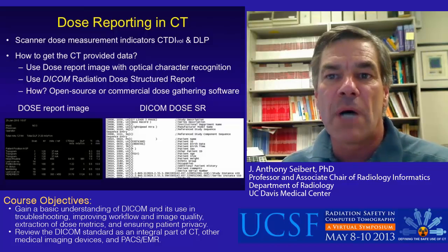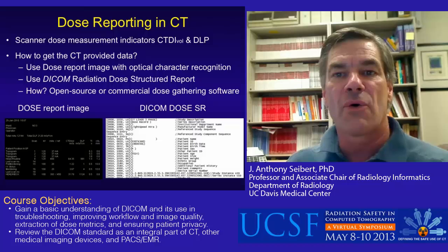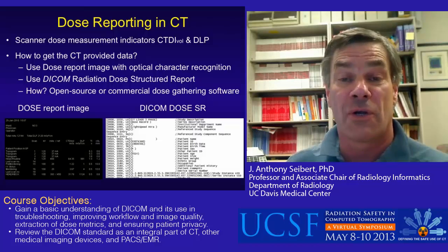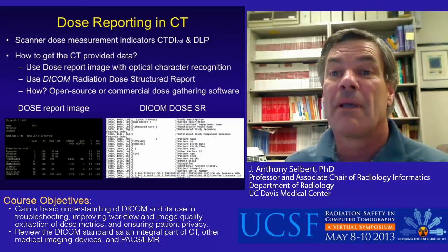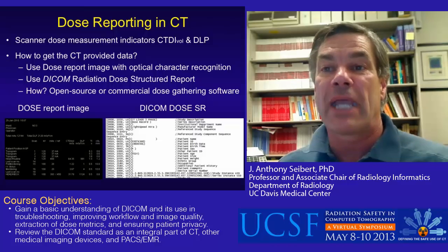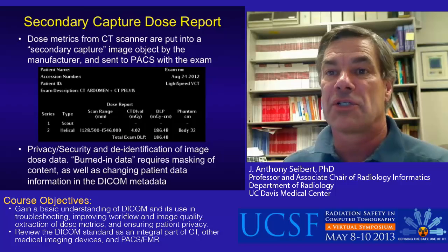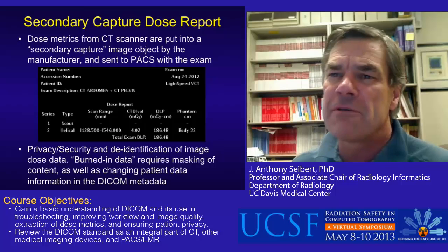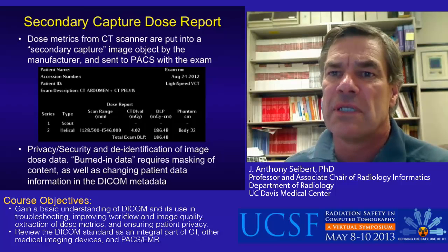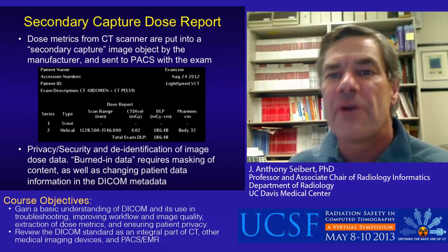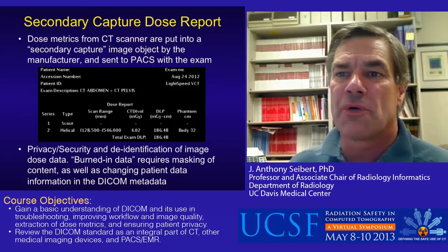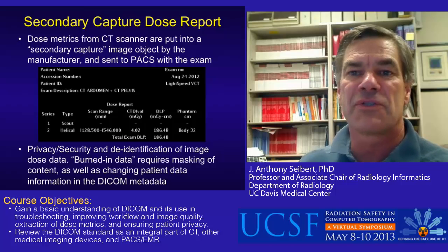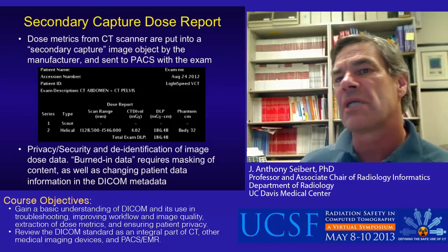The RDSR is a relatively new module, and the unique identifier descriptor is not always acknowledged in a PACS, nor is it translatable in a universal way, at least currently. However, the dose report image is a secondary capture object which requires optical character recognition software to automate the extraction of dose information into a character format. Often, protected health information is burned into the dose report image, making it very difficult to anonymize the study. The dose report shown here is de-identified by using masking software to eliminate patient-identifiable values such as patient name, accession number, and patient ID or medical record number.